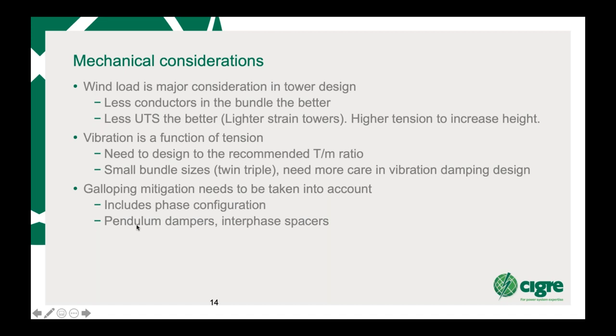Then you could also use pendulum dampers, which avoid the formation of the aerofoil, as well as interphase spacers, which are quite important to just hold the phases away from each other so that they don't cause spark over.